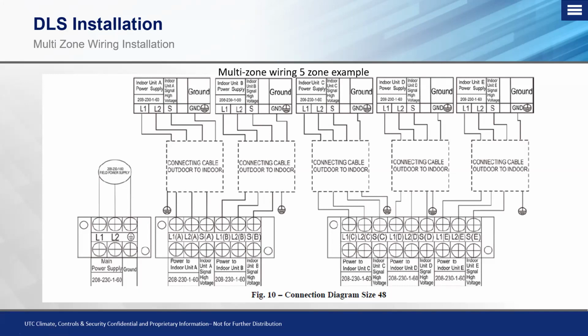As the system starts to satisfy and we start getting different zones coming on at different times, we're going to send refrigerant out to a zone that isn't calling for it, and it can cause, in cooling mode, icing up on the coil, or in heating mode, it's going to pretty much not heat at all. So we'll get into that in a minute, but again, the most important part to take out of this: label your power and your control wires. Otherwise, you are going to run into a multitude of headaches.